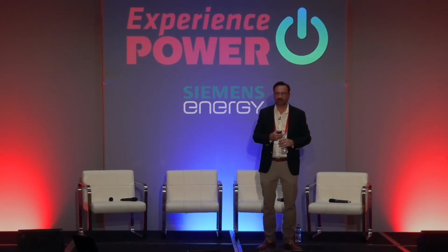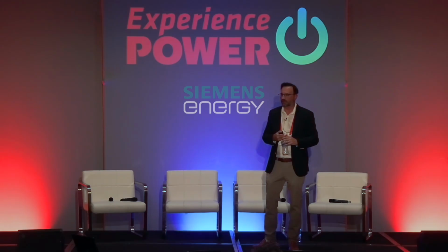So 5 minutes ago, I just sent you a plan of how to operate for 24 hours, and now I'm sending you a new plan of how to operate for the next 24 hours, right? And this is called the rolling time horizon. This is a way that we can keep the power plant in a continuous state of optimization, always using the latest information to account for things that can't be forecast or unforeseen circumstances. Okay, so those are really the key elements behind an energy management solution, right? The simulation, the forecasting, and the optimization.